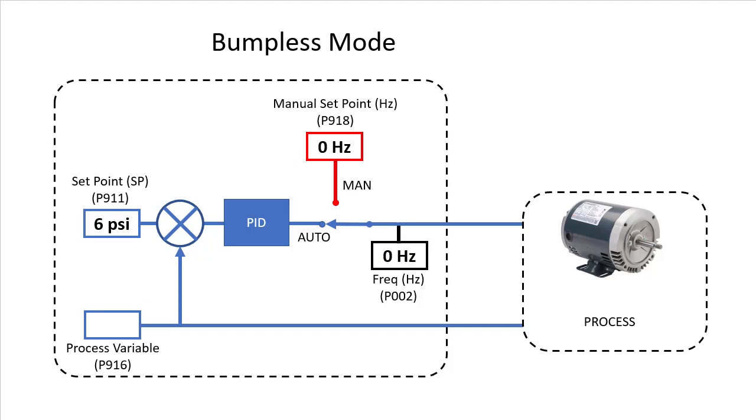PID is going to try to get the process to 6 psi as fast as it can, which usually means it will send the motor straight to its max speed until the pressure gets close to its desired value and then back off on the motor speed so the process settles out right at the set point.